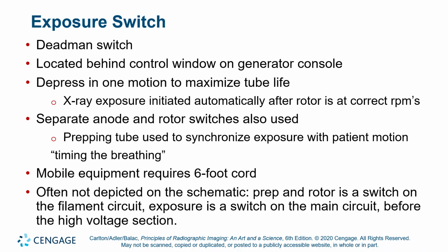Okay. On room built equipment like in an X-ray room, the exposure switch is short, so you stay behind the control panel. On mobile equipment, the exposure switch is either long or remote control. Both of these are radiation protection. We want a long exposure switch, a long cord on our portable machine so we can step out of the room because we don't have a lead barrier control booth. Okay.